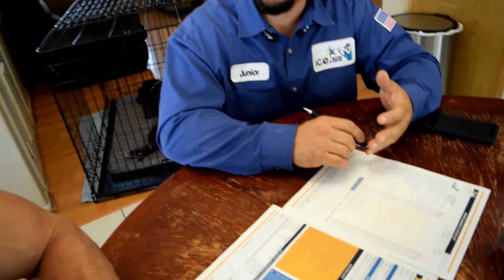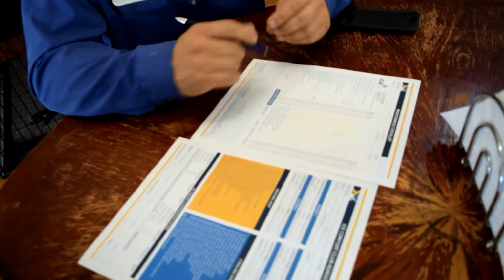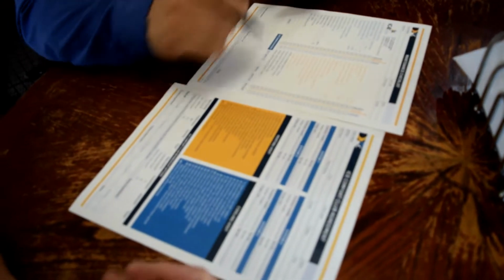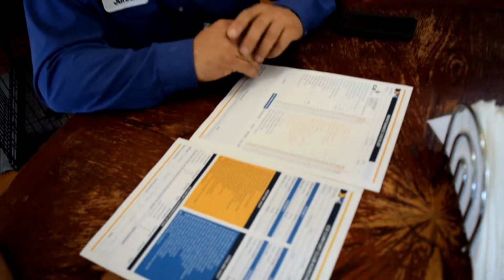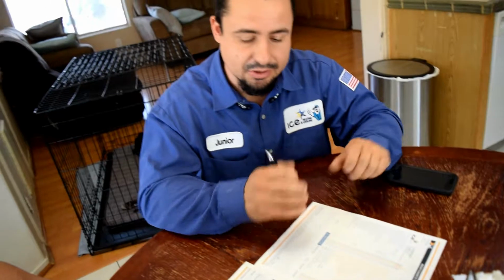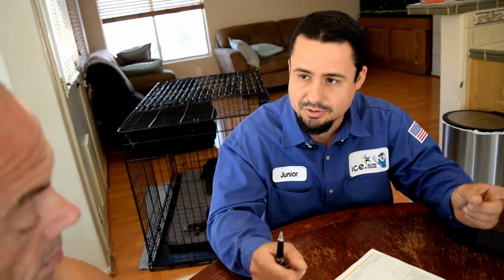In about six months we'll come back and do a heating visit, which is more about safety. We'll check your gas pressures, make sure there are no gas leaks, do a carbon monoxide test, and make sure your system is exhausting all the fumes out of your house. We'll adjust your pressures and look at your temperatures, so your system is running efficiently and your family is safe.